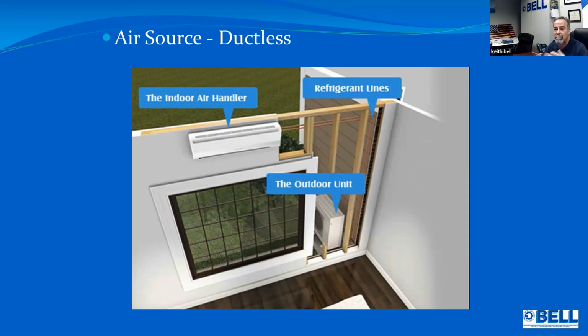So the two different main sources: an air source heat pump and a ground source heat pump. An air source heat pump has to reject that heat into 90-degree air outside in the summer. And in the wintertime, basically you reverse that flow. So now you're blowing hot air inside the house and you're pulling heat from outside to bring it into your house. And even though people say, oh, it's electric heat, it's electric powered, it's multiplied by how much heat you're getting from outside. It uses the refrigeration cycle to do that.